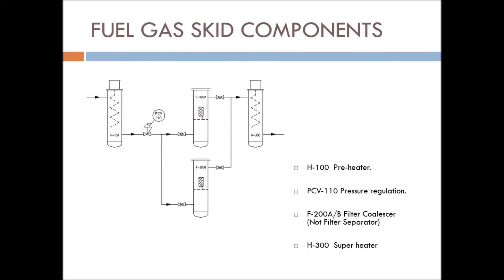Here is a simple fuel gas conditioning system, which has a preheater to prevent hydrate formation, a pressure reduction station to get the proper inlet pressure for the gas turbine, a duplex filter coalescer for switching while it's running, and a fuel gas super heater to raise the gas temperature well above its dew point. The gas will take additional pressure drops in the fuel management system.